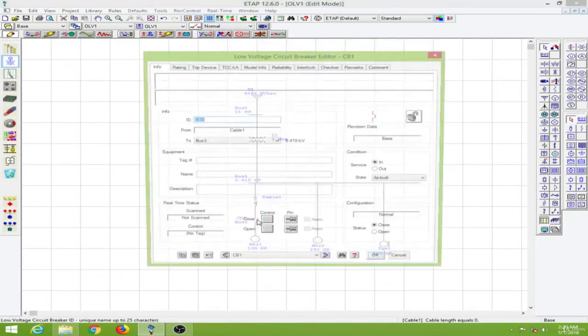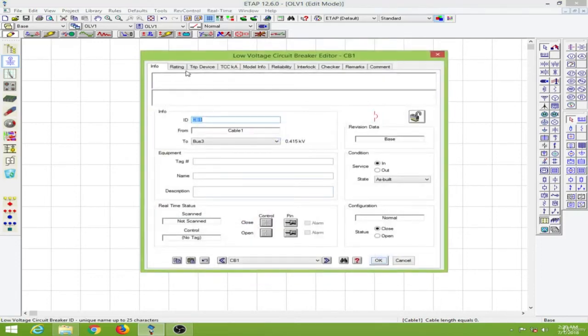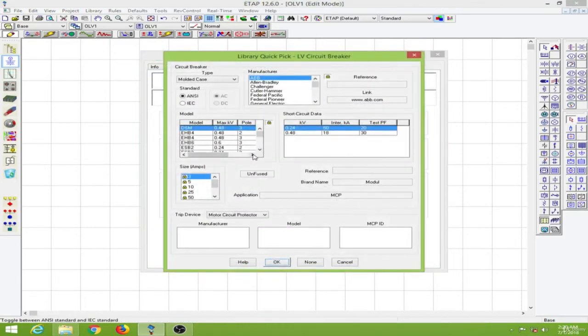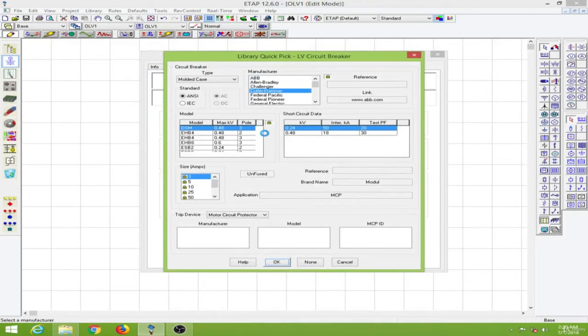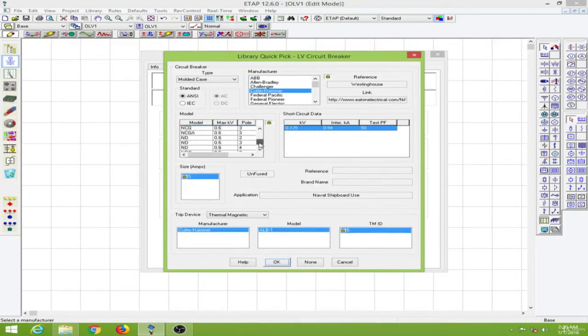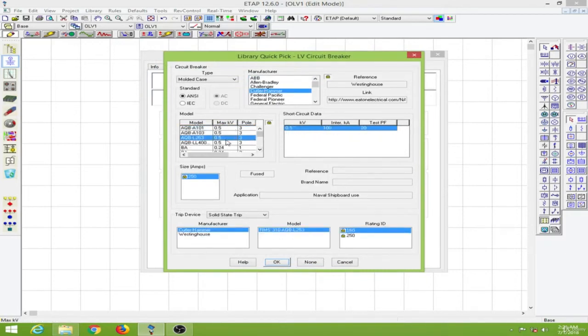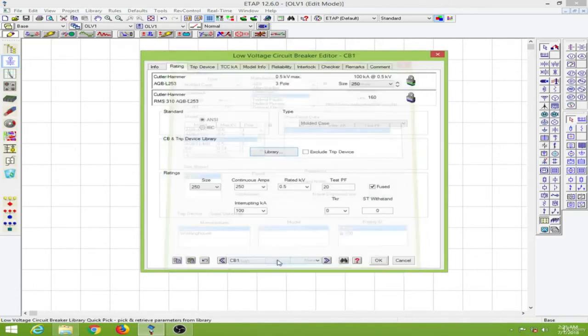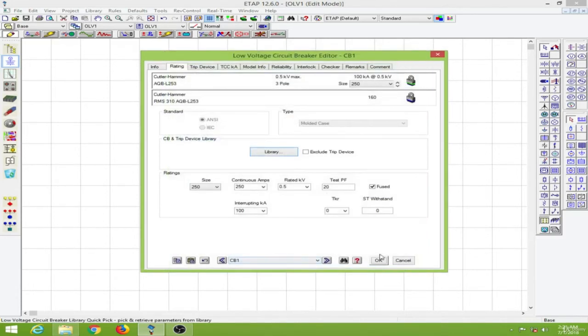Now to write my circuit breaker over here. So double clicking, go to the rating page. I had to pick a 200 amp circuit breaker. Over here we have the 250 amp circuit breaker so I will choose this. And the trip device will be the Cutler Hammer. And everything else I will keep the same and I will click on OK.